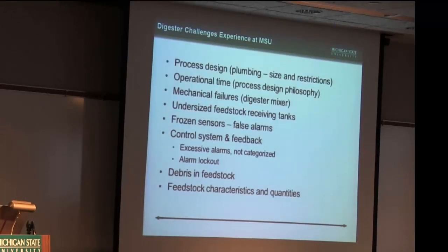From our standpoint, we're now taking in more feedstock than we expected, so our receiving area is undersized. We've had freezing issues. Of course, last winter was extremely harsh. We learned a lot quickly. Controls continue to be a bit of an issue. We get a lot of lockouts and a lot of false alarms. Debris in the feedstock is always a challenge.